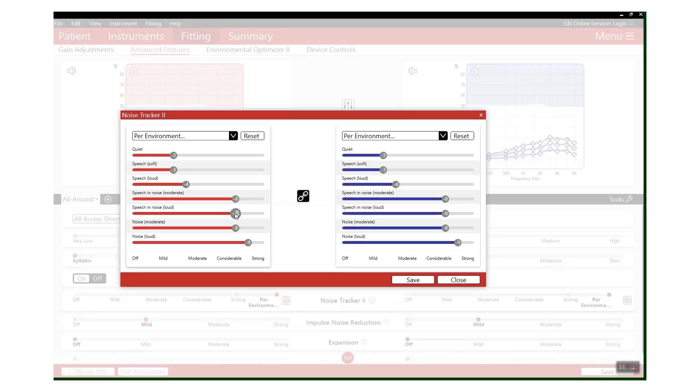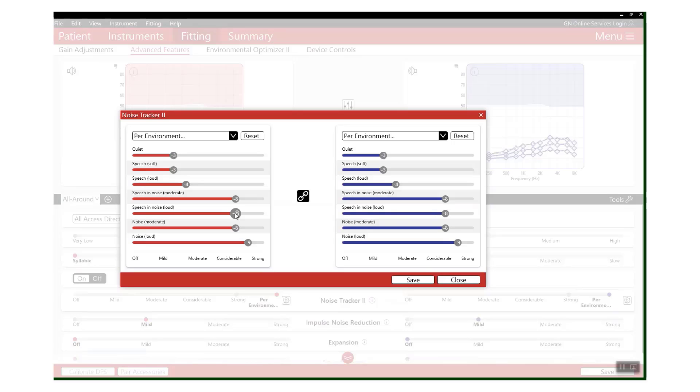Now what we've learned since then is that our noise reduction uses spectral subtraction, so it maintains the speech signal and we're only going to reduce background noise here. So the gain we applied to the speech stays the same, however we're now reducing our background noise, and therefore we've increased our signal to noise ratio. The speech is now at a much higher level than the background noise, and hopefully your patient will be able to go into these environments and focus on conversation much better than before.